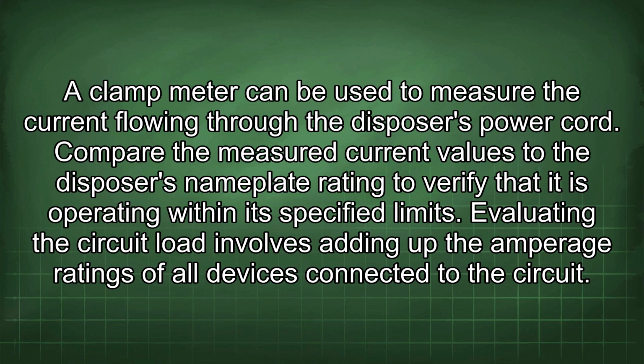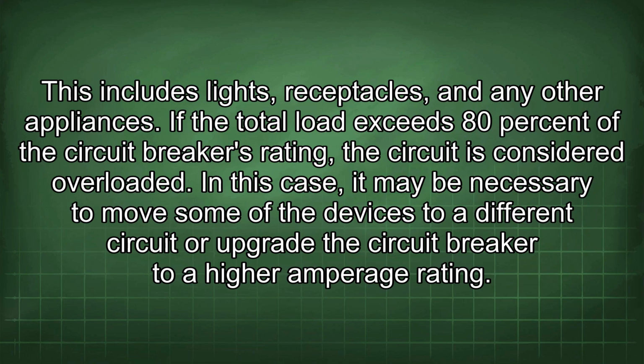Evaluating the circuit load involves adding up the amperage ratings of all devices connected to the circuit. This includes lights, receptacles, and any other appliances. If the total load exceeds 80% of the circuit breaker's rating, the circuit is considered overloaded. In this case, it may be necessary to move some of the devices to a different circuit or upgrade the circuit breaker to a higher amperage rating.